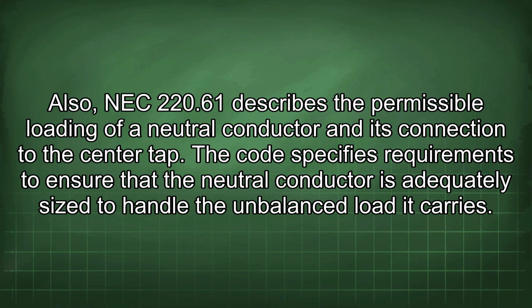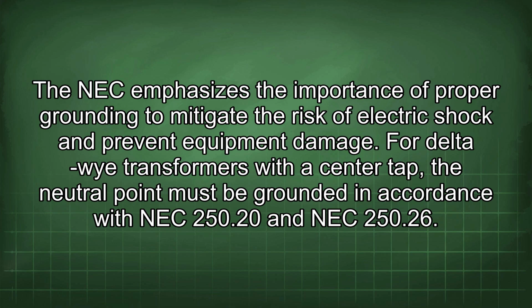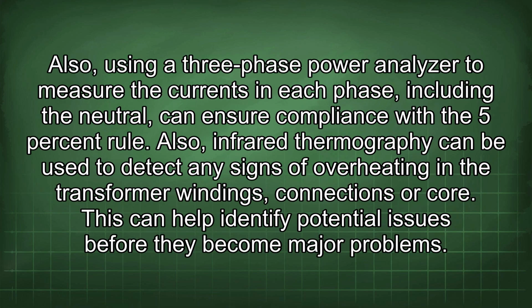Also, NEC 220.61 describes the permissible loading of a neutral conductor and its connection to the center tap. The code specifies requirements to ensure that the neutral conductor is adequately sized to handle the unbalanced load it carries. The NEC emphasizes the importance of proper grounding to mitigate the risk of electric shock and prevent equipment damage. For delta Y transformers with a center tap, the neutral point must be grounded in accordance with NEC 250.20 and NEC 250.26.